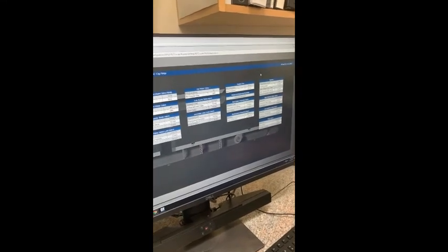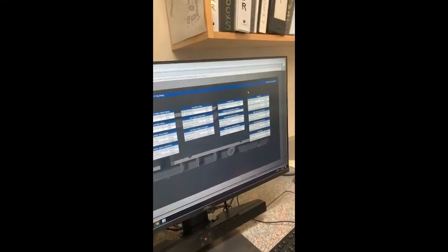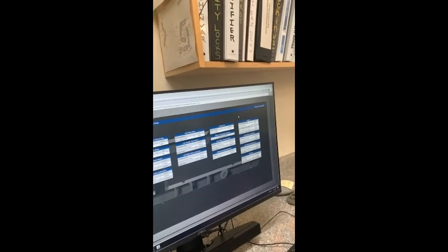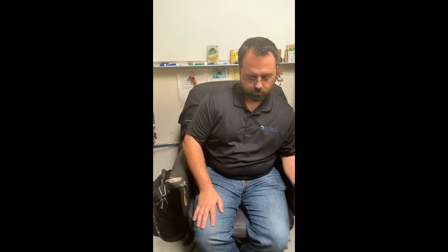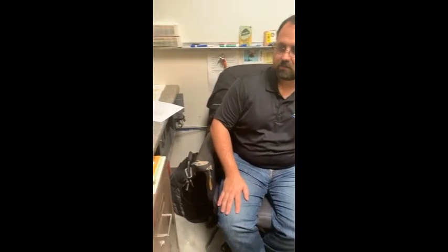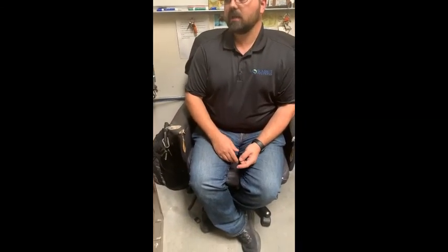You can set the min and max frequencies. The minimum you can set, the maximum you cannot change. The maximum is set by the unit manufacturer, and they're all different. Like one's 81, 167, and 161 maybe. But I know they're all slightly different, and they're all weird, like 81 hertz. I'm not sure how they came up with those numbers, but it's actually listed on the name tag of the unit. Right. Yeah. Mike told us about that. We do let each unit go up to it.